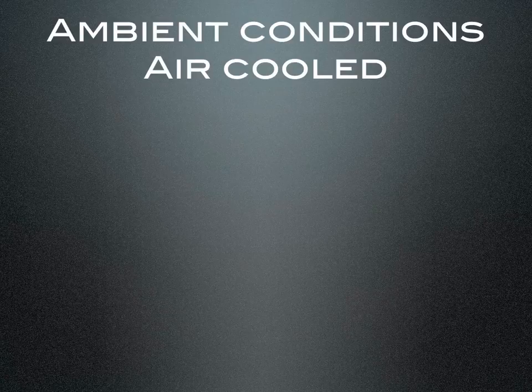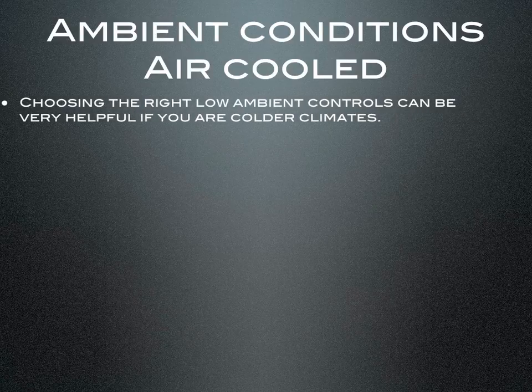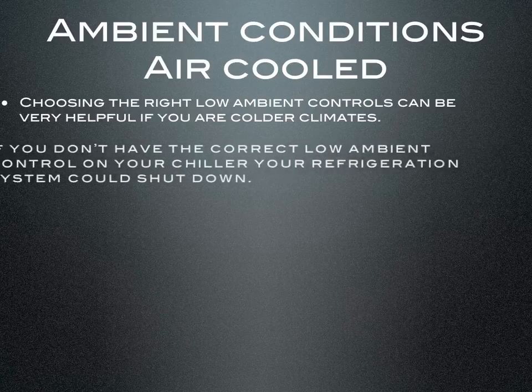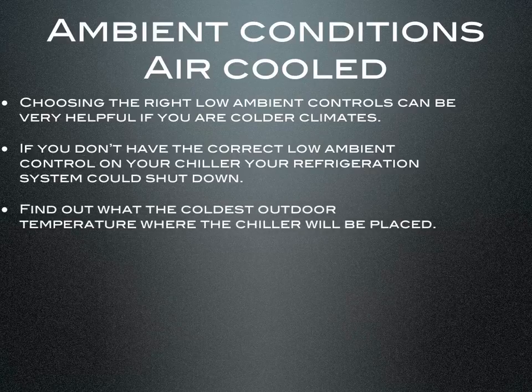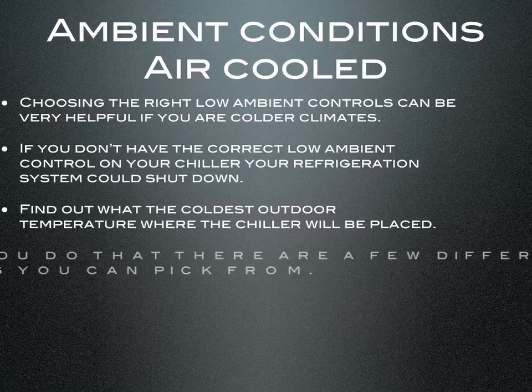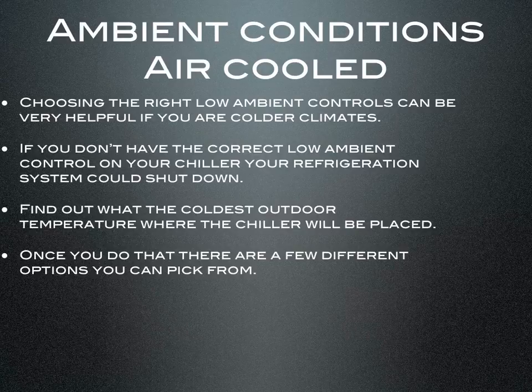Let's talk about ambient conditions for air cooled chillers if your chiller is outside. Choosing the right low ambient controls can be very helpful if you are in colder climates. If you don't have the correct low ambient control on your chiller, your refrigeration system could shut down. You need to find out the coldest outdoor temperature where the chiller will be placed — there are different options depending on whether your coldest outdoor ambient is 40, 20, or even minus 30 degrees.